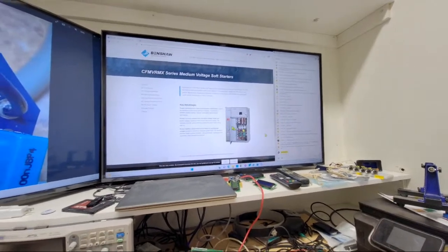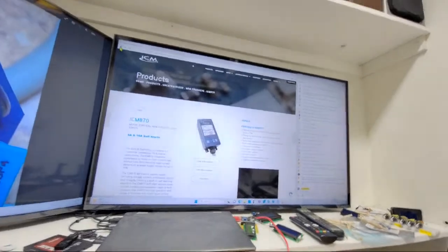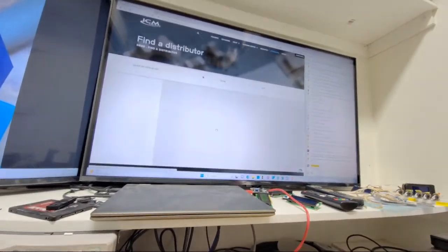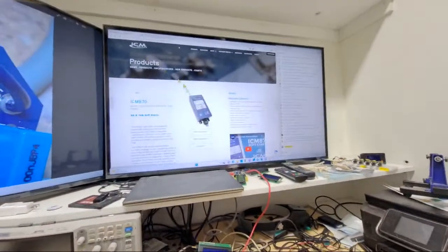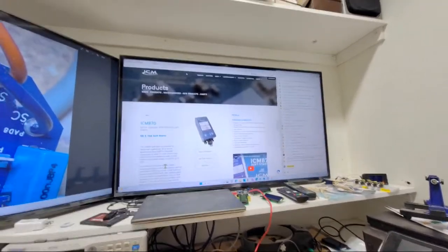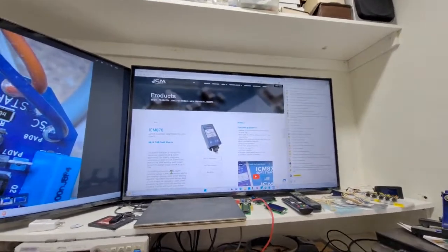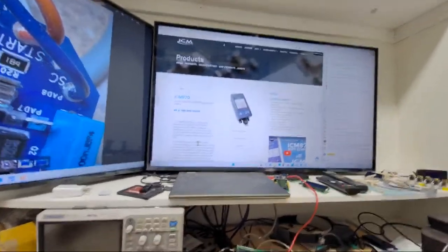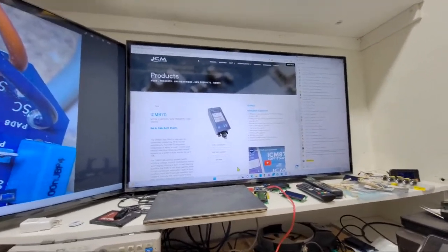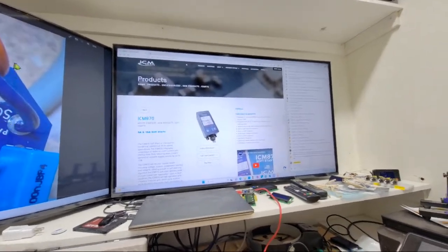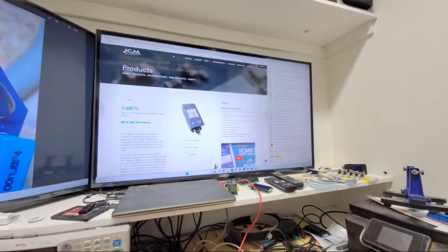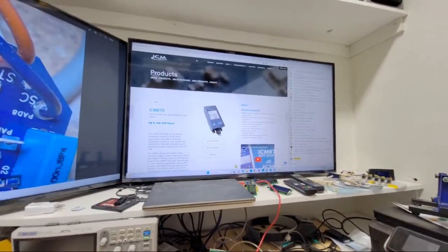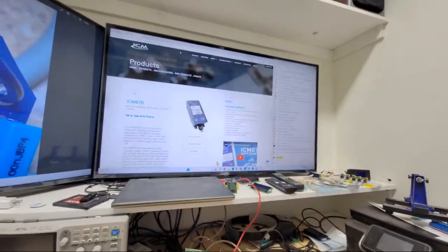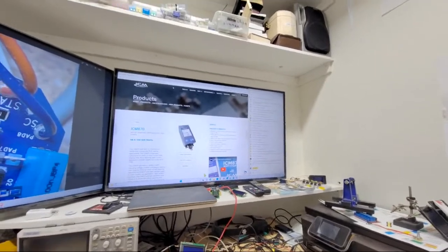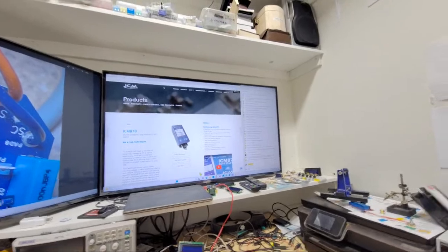Anyway, soft starter's cheaper, he says. Let's see where that was - find a distributor, well I wouldn't, this probably isn't gonna tell me, but you'll have to go look. I think for somebody whose generator just has a little too much trouble starting, they slap this thing on if they can figure out the controls. Look at the instructions - a lot of do-it-yourselfers are doing this because they're desperate, and they're probably screwing their stuff up, because it's generic instructions saying if your unit looks like this with this color wire. Again, do-it-yourselfers doing this is probably not the best thing. But if they didn't have a good hard start, just adding a hard start kit could make all the difference - putting a proper 521 on their little rotary compressor on an RV, or someone's small single phase AC that didn't have that and is trying to start off a generator or inverter. Just adding the good 521 might be all they needed.